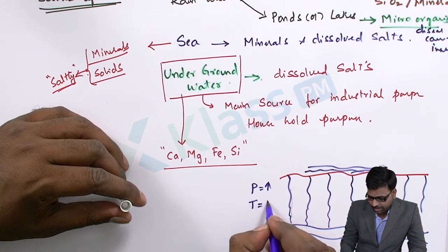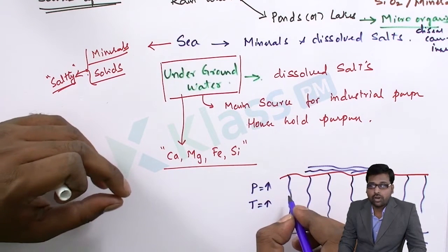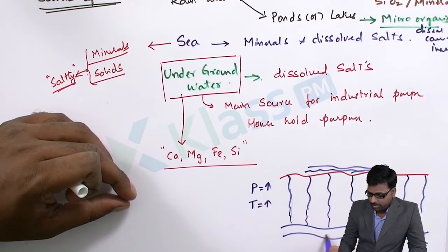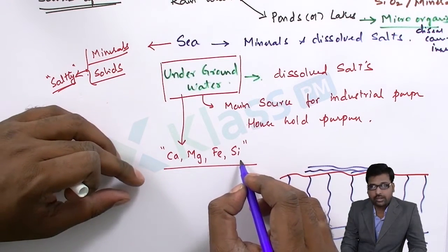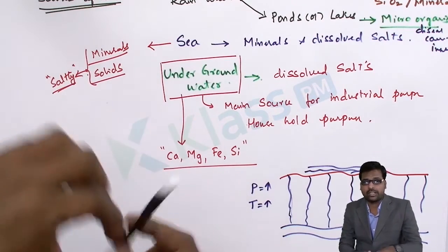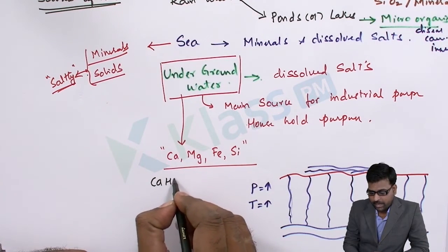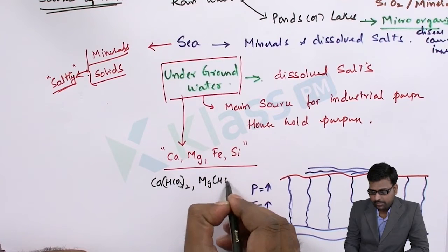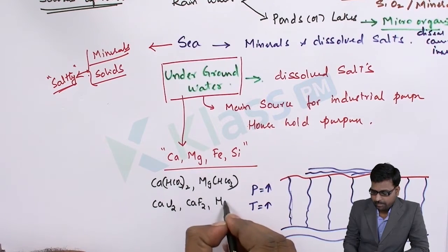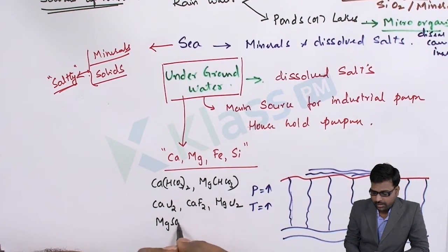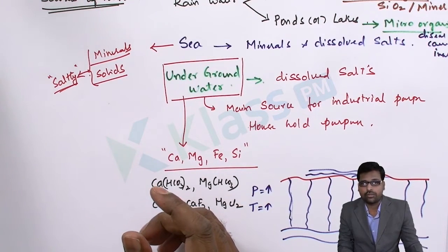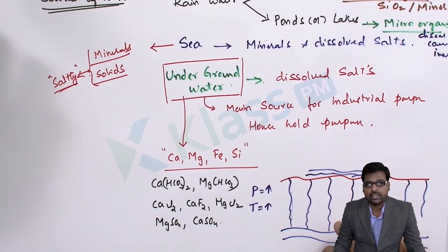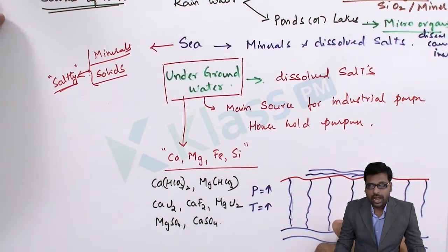Because of high pressure and increased temperatures, the water dissolves whatever salts it comes across in between, and these salts accumulate in the underground water — salts of calcium, magnesium, iron, and in some cases silica. The specific salts are: calcium bicarbonate, magnesium bicarbonate, calcium chloride, calcium fluoride, magnesium chloride, magnesium sulfate, and calcium sulfate. These salts are the main hardness-causing salts of underground water, which is the main source for industrial purposes.